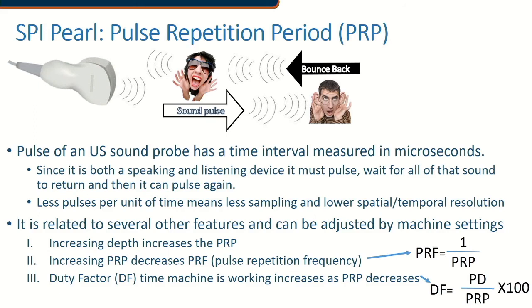Therefore, if you have deeper shots, you're going to have less pulses per unit of time as you wait for them to come back from deeper depths of your shot. Therefore, when you go deeper into your shooting, you're going to have a lower spatial or temporal resolution because you've increased your pulse repetition period. It's related to a couple other features of ultrasound that can be adjusted by the machine, which is why it's so important that you understand PRP. If I increase my depth, I increase my PRP. We've just talked about why that is.